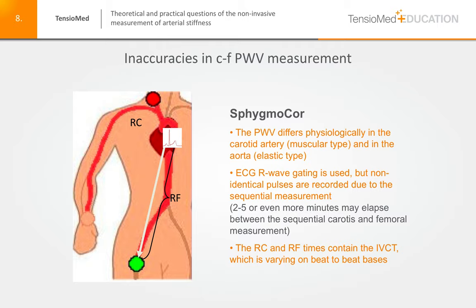The aplanation tonometric method — the SphygmoCor method — uses ECG gating to determine the aortic pulse wave velocity, or more precisely the carotid-femoral pulse velocity. Because of using ECG gating, the problem with the opposite direction is eliminated, because this method measures the R-wave-to-femoral time and the R-wave-to-carotid time, and R-C is subtracted from R-F. Thus, the true aortic pulse wave velocity transit time can be determined.